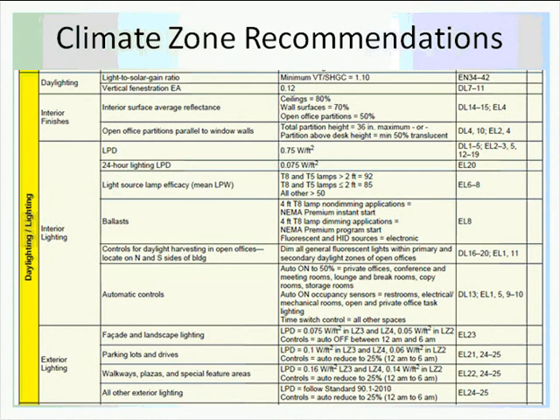On the efficiencies of the lamps, we're seeing T8 and T5 technologies with high-performance lamps that produce around 3,100 lumens, around 92 mean lumens per watt. We are not eliminating all other sources besides fluorescent; there are opportunities for compact fluorescent, ceramic metal halide, and LEDs. We'd really like to keep the incandescents out of there. So we still allow efficiencies of around 50 lumens per watt for other sources. For the ballast, there have been some increases since the 30% guide to the NEMA Premium type ballast. These use about 3 to 5% less energy than the standard electronic ballast out there.